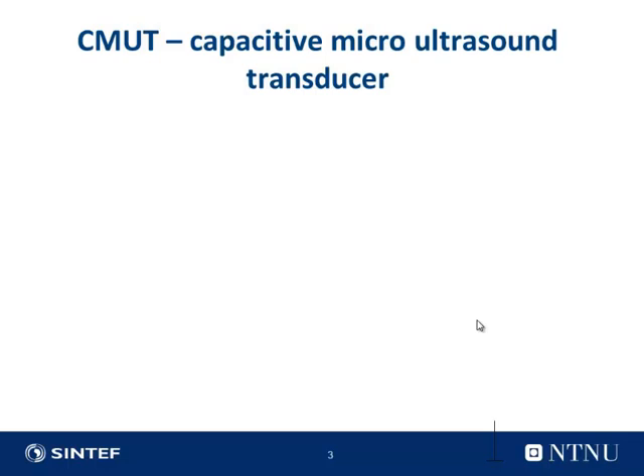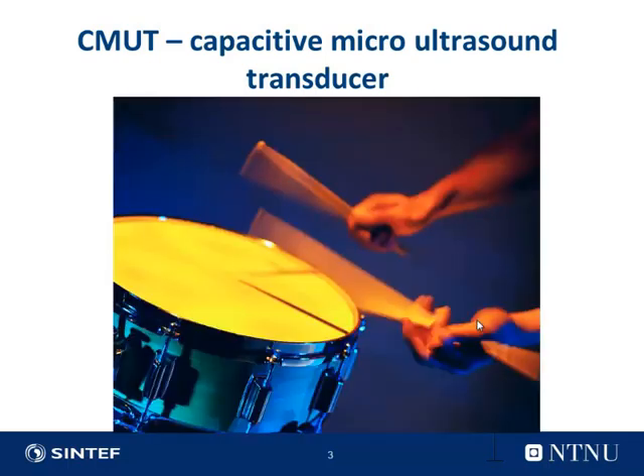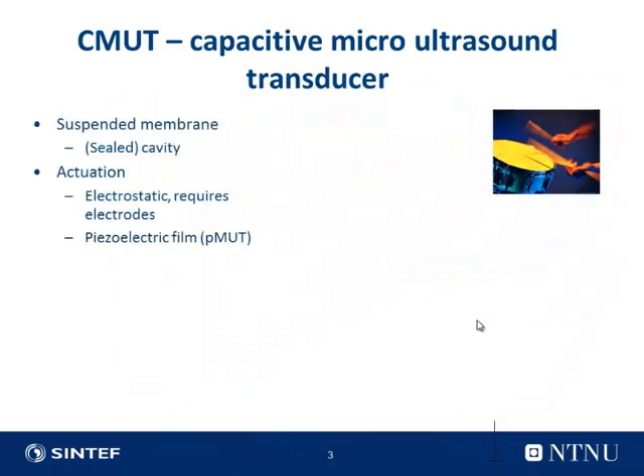A wider frequency band is also desirable. So here's where the CMUT comes in. A CMUT is basically a drum that is actuated by electrostatic forces. You need a suspended membrane, preferably with a sealed cavity if it's to be used outside of air, and of course you also need the electrodes for activation. You can choose here between MEMS fabrication with bulk and surface micromachining. We believe bulk micromachining, at least for these frequencies, is the best because you can use high quality materials and you get better material properties.